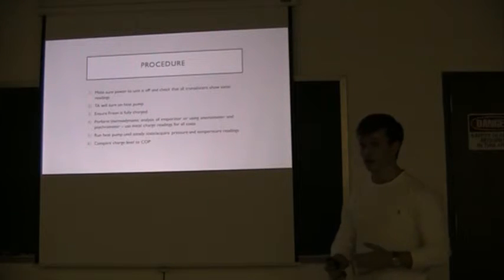So our procedure, we're going to run a few different times through. We're going to start off with fully charged. So we're going to charge the Freon unit as much as we can. And then we're going to run through and steadily drop down to about 14 pounds. And we're going to record that data through each of those cycles. And we're also going to use a psychrometer and anemometer to perform an evaluation on the evaporator itself.